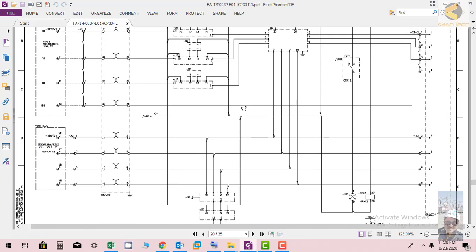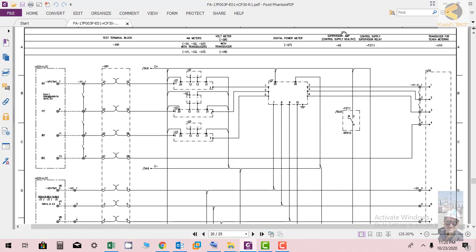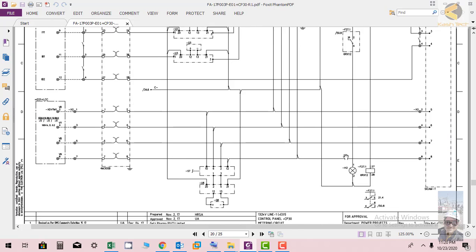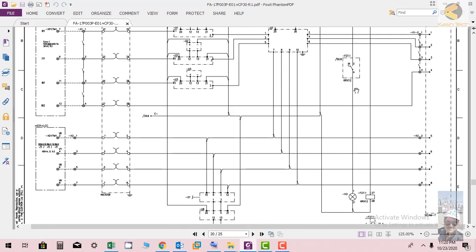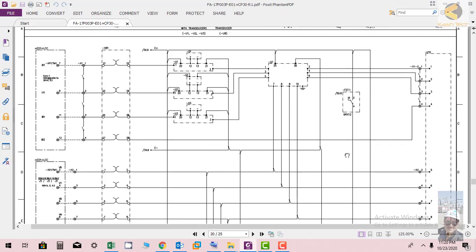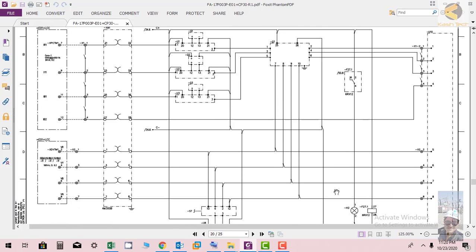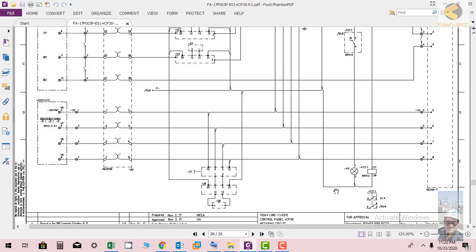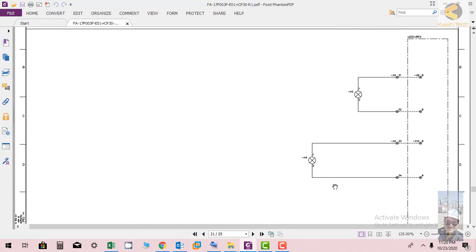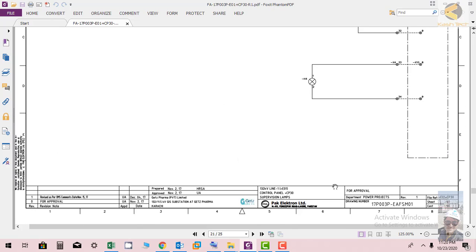Then here you can see we have supervision lamp control supply healthy, which is showing the supply is healthy. When 27 1.1 is picked up, the light will be on showing continuously the supply is healthy. This relay is monitoring the control supply at the end of the loop.